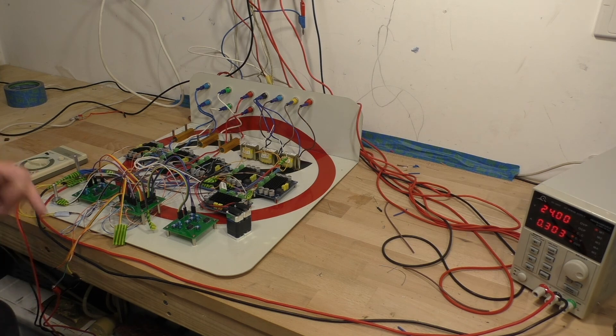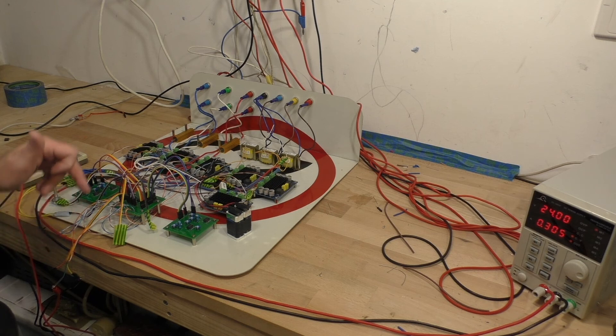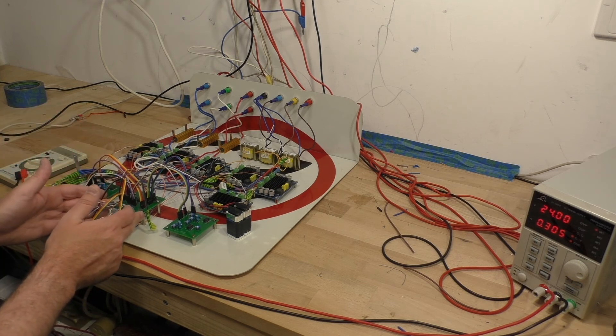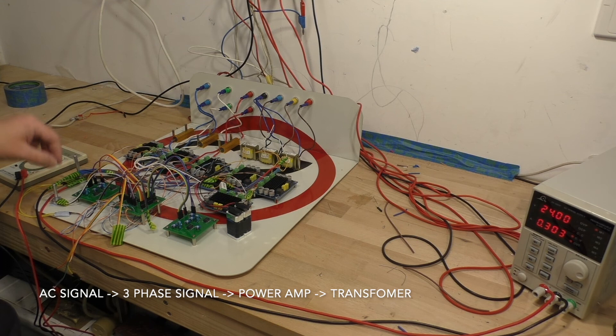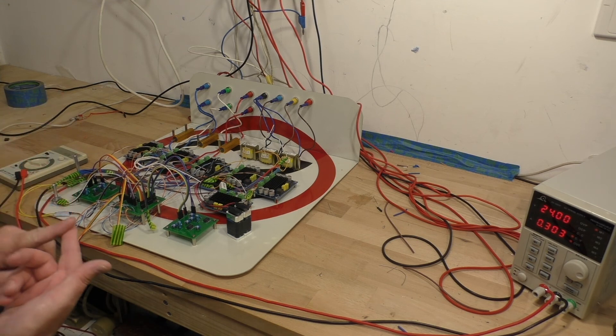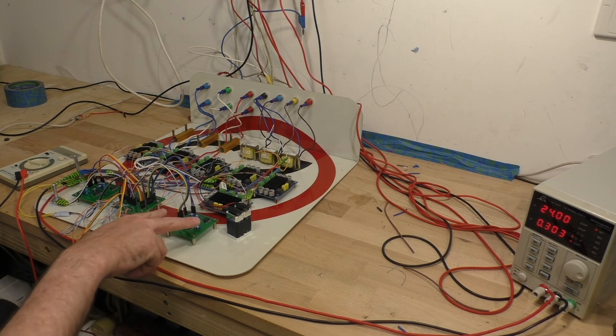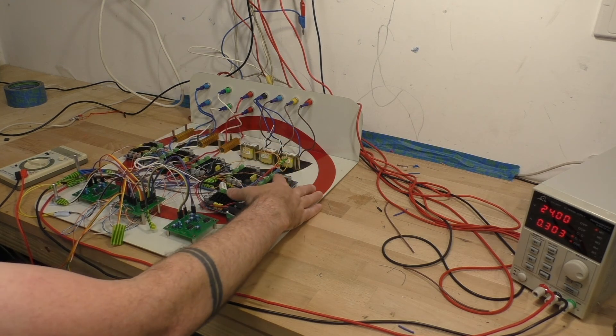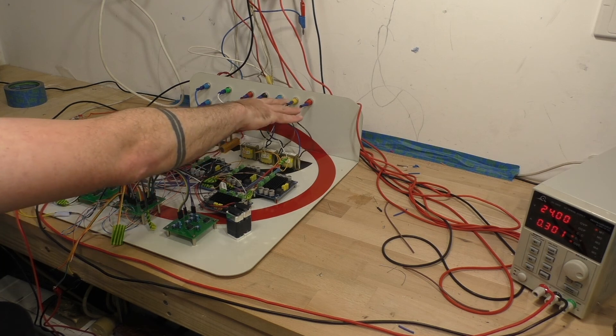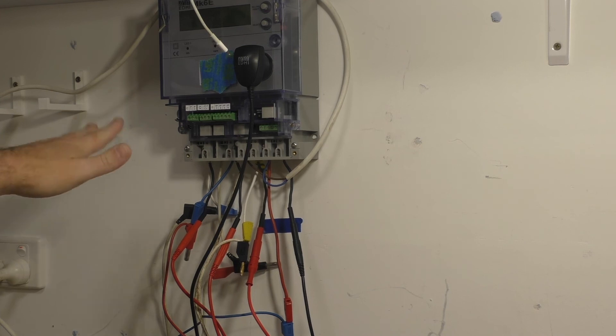What we've got is a 50 Hertz sine wave comes in to this board, goes from this board, splits over to a voltage signal board and to a current signal board. I can shift using these two potentiometers amplitude and phase angle. From the voltage signal board it goes out through power amps, transformers into a star output. You could technically hook it up as a delta if you wanted, but it's got star into this Mark 6E EDMI energy meter. That's what's giving me the feedback.